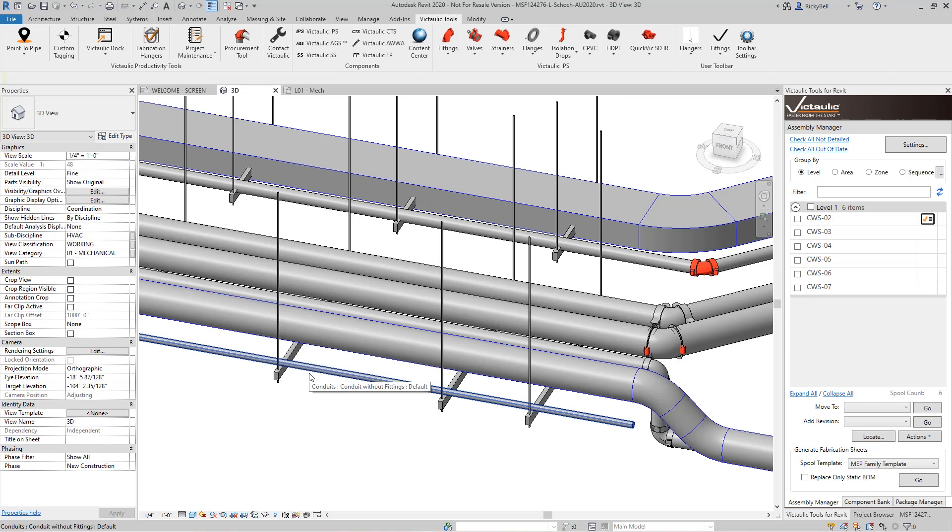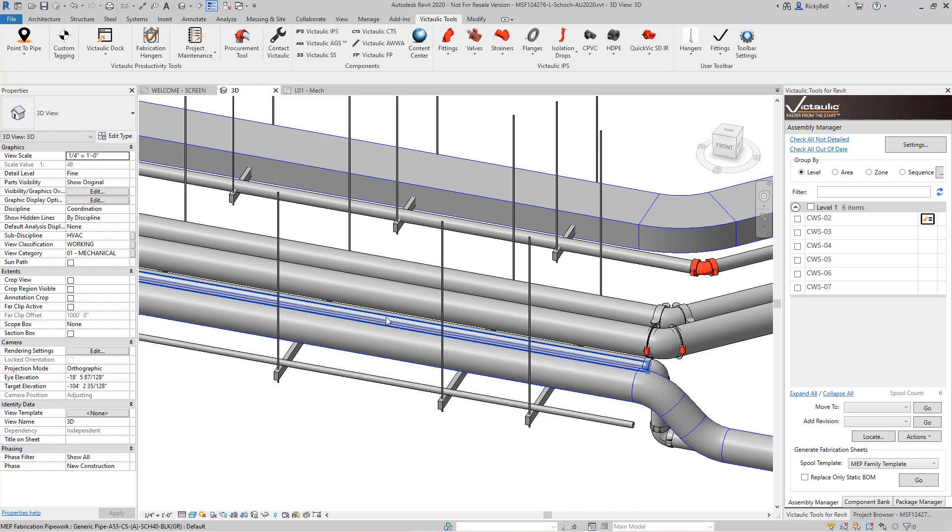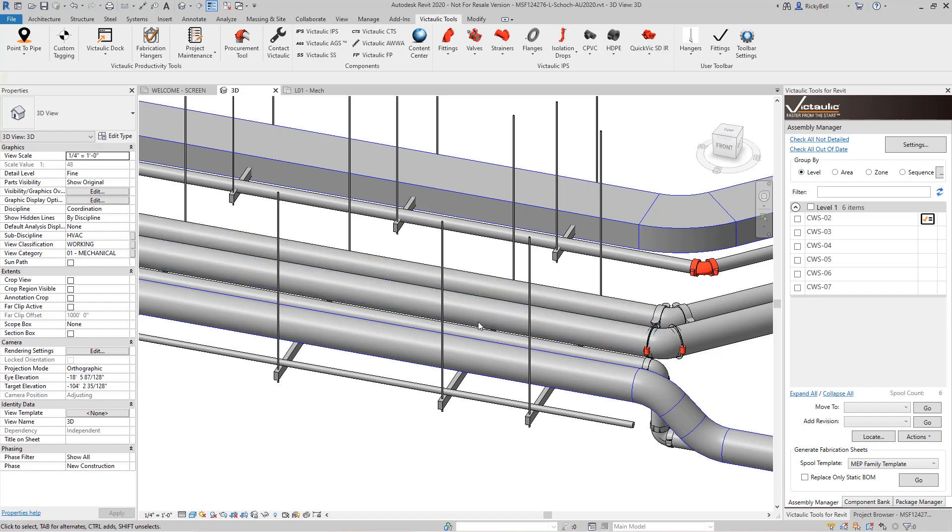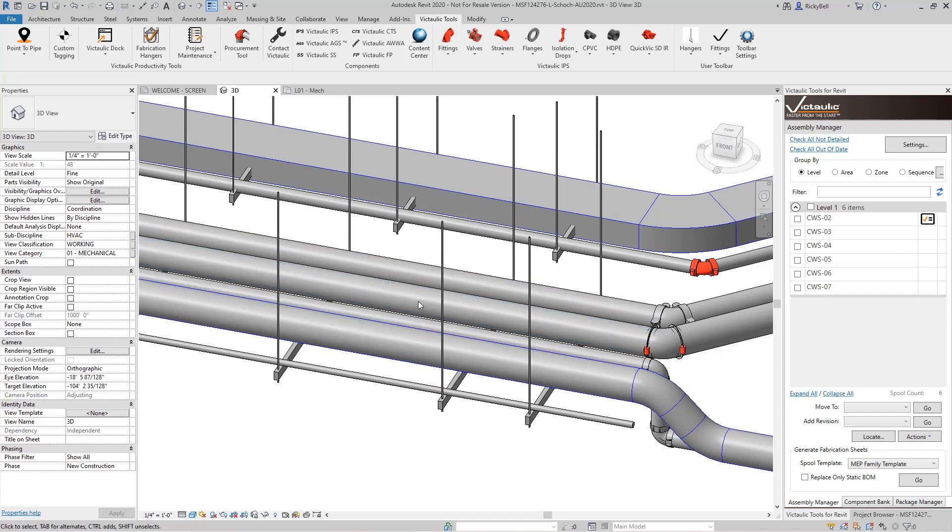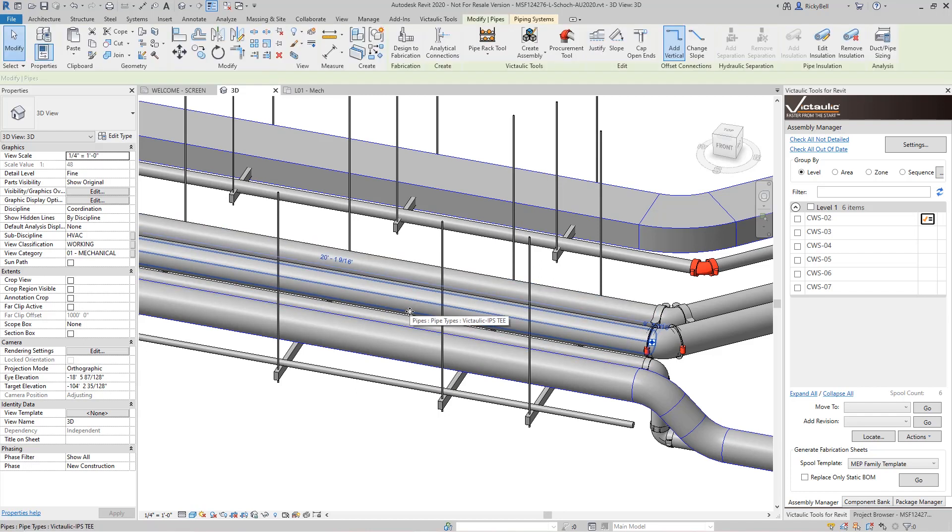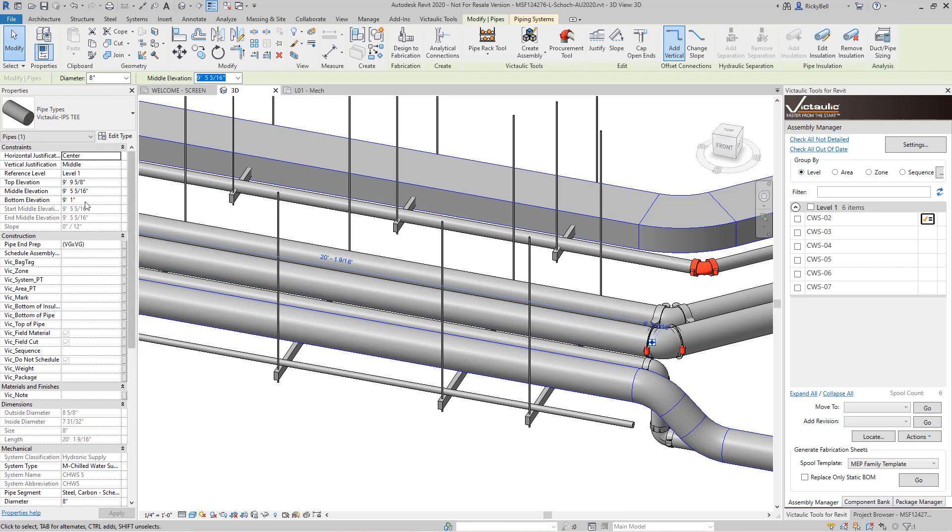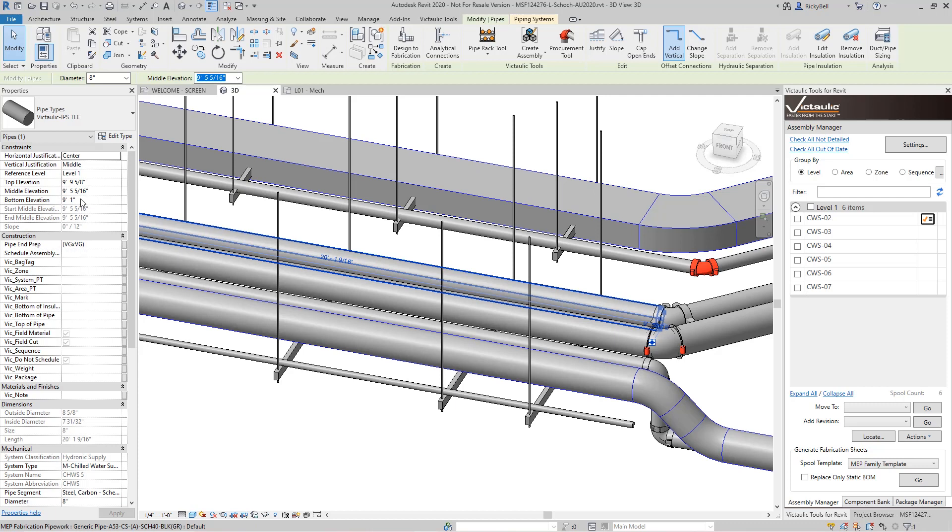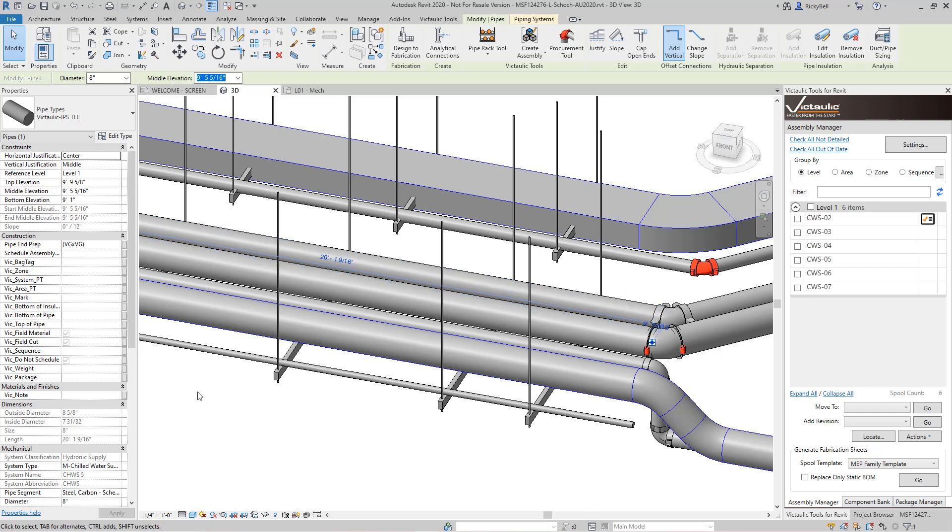Now let's take a look. The conduit is placed right on top of the hanger. This round duct is placed right on top of the hanger. All of these other ones that have or do not have insulation are placed properly, where you can see that their center lines are far above nine feet. This one has one inch of insulation, so the bottom elevation is set to nine foot one. And that makes perfect sense because we want it to be resting on the hanger, not conflicting with the hanger.